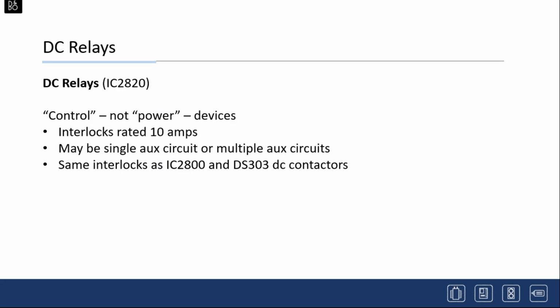Now, I talked about DC relays, and I wanted to take a minute to mention them, which go by the nomenclature IC2820. Notice these are control, not power devices. The interlocks are generally rated at 10 amps, and can be a single auxiliary circuit or multiple. Some of our DC relays have 10 or 12 auxiliary circuits. As information, the interlock used on the power contactors, the IC2800s or DS303s, is the same relay interlock used on the 2820s. So you have common renewal parts between the DC relays and the DC contactors.